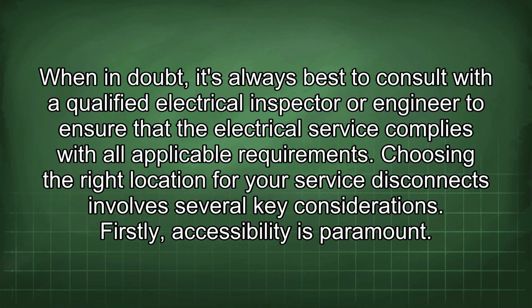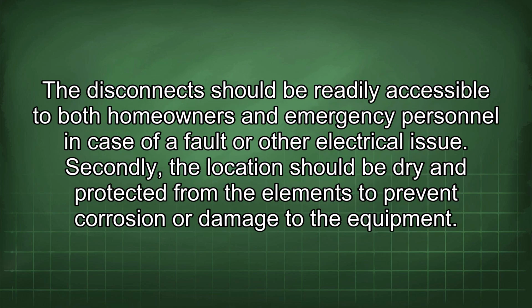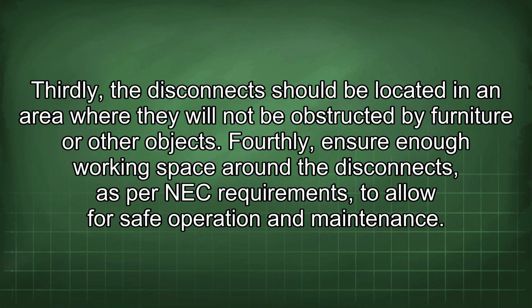Choosing the right location for your service disconnects involves several key considerations. Firstly, accessibility is paramount. The disconnect should be readily accessible to both homeowners and emergency personnel in case of a fault or other electrical issue. Secondly, the location should be dry and protected from the elements to prevent corrosion or damage to the equipment. Thirdly, the disconnects should be located in an area where they will not be obstructed by furniture or other objects. Fourthly, ensure enough working space around the disconnects, as per NEC requirements, to allow for safe operation and maintenance.